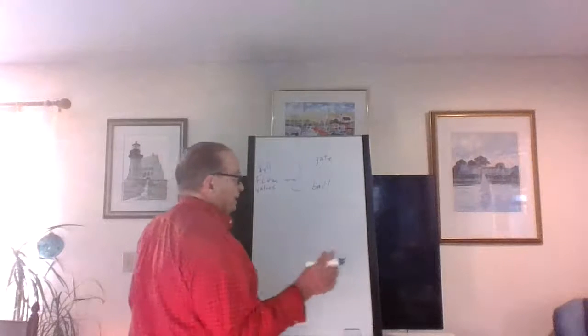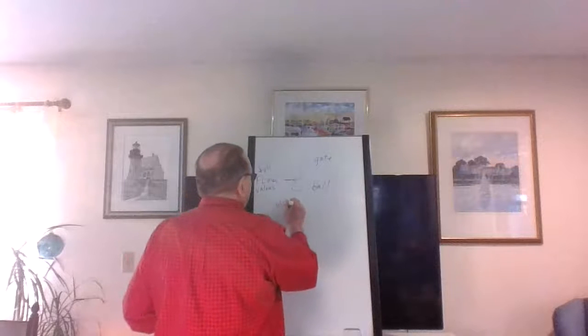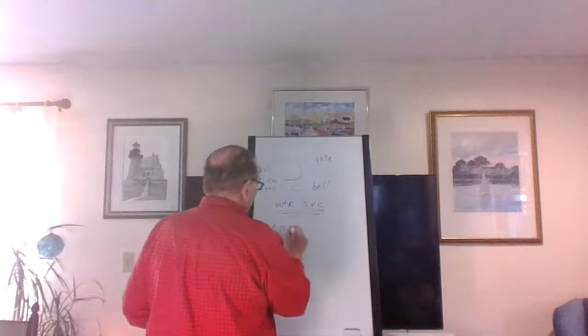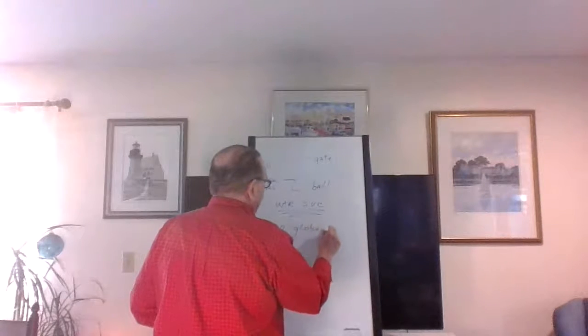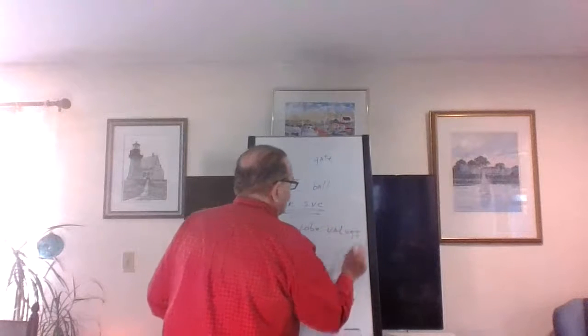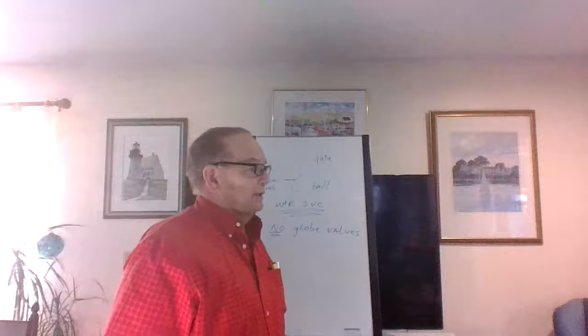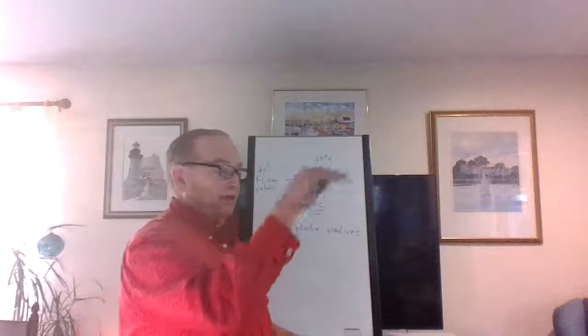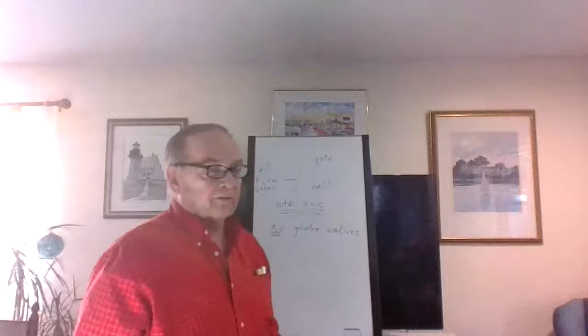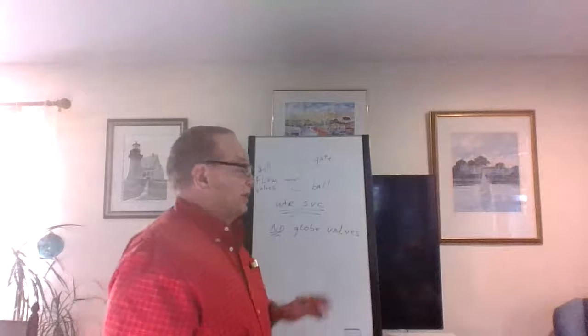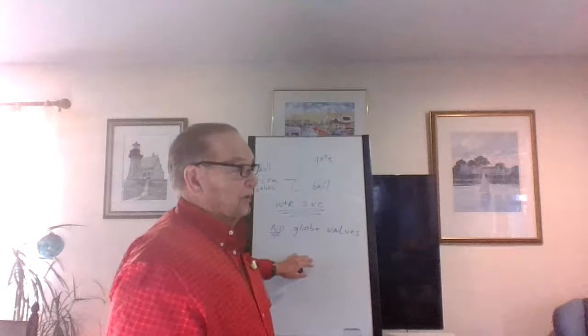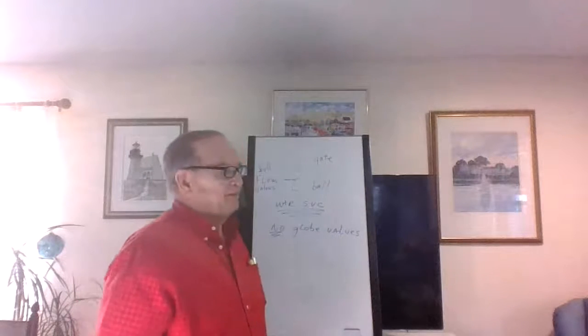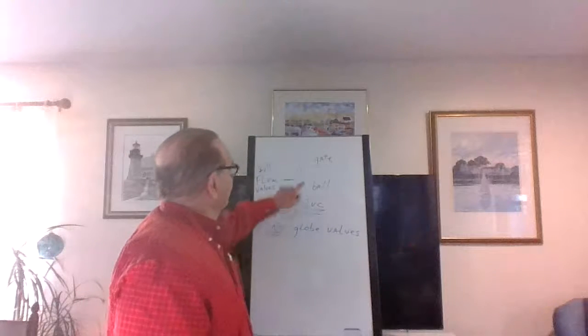No globe valves. A globe valve would be like a stop and waste or any of those other valves where you look in the valve and you can't see through the other side because it goes in and does kind of one of these things. It's too restrictive. They do make a stop and waste like three-quarter inch and I've seen somebody try to slide one by when I was an inspector. Little Compton is like, that's not a legitimate valve.